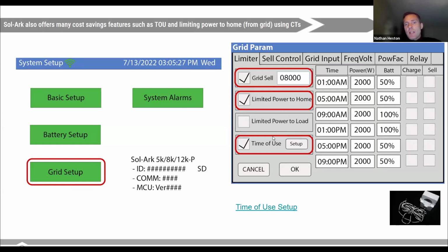And then time of use settings, as I talked about a little bit earlier, allow you to export or import power from the AC bus into the battery. In the example shown here with this time of use box checked, you can also set up seasons by clicking the setup. By checking this box, I can specify, if I check the charge box, that I want to charge my battery between 1 a.m. and 5 a.m. at 2,000 watts.